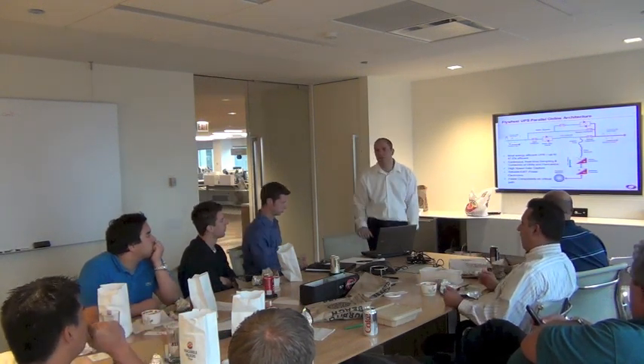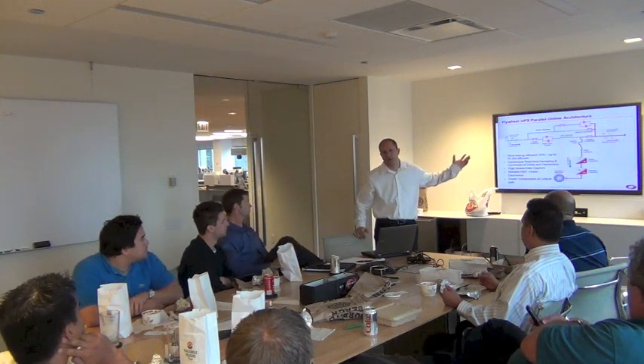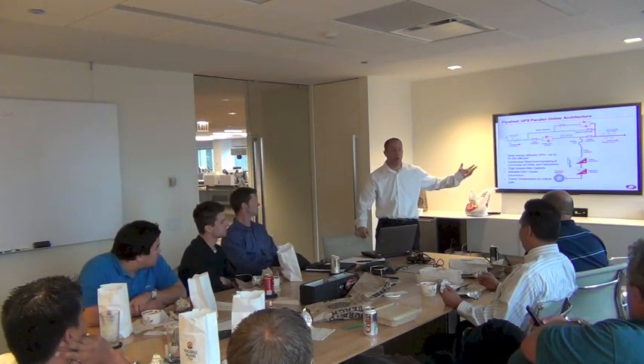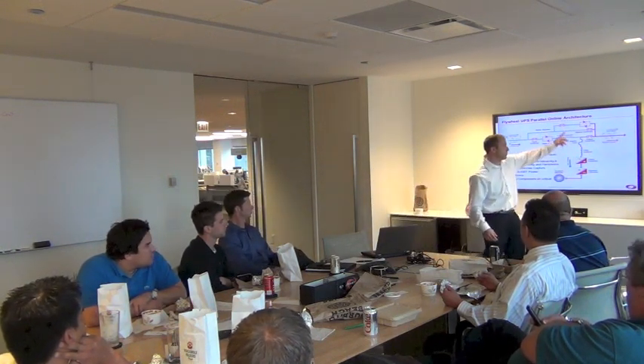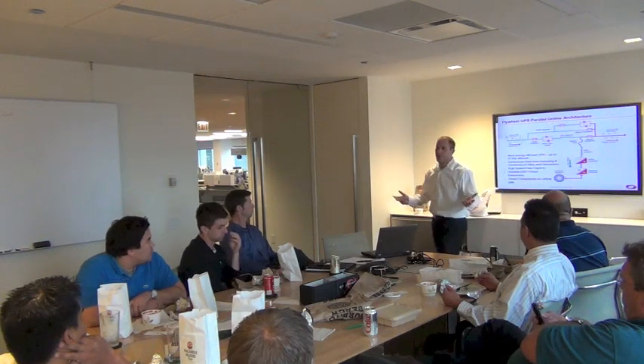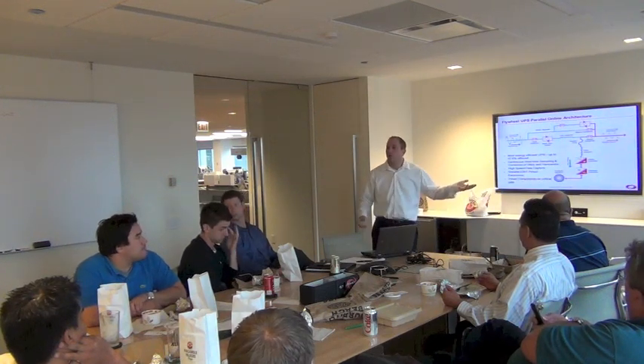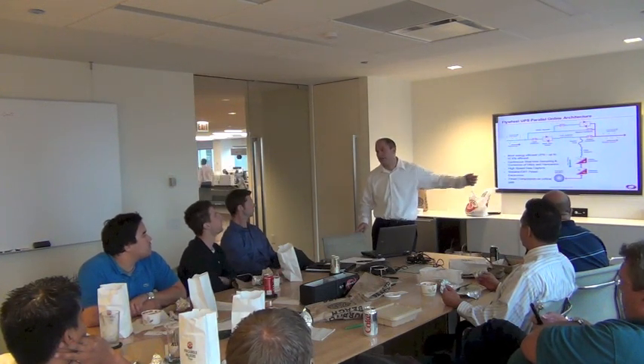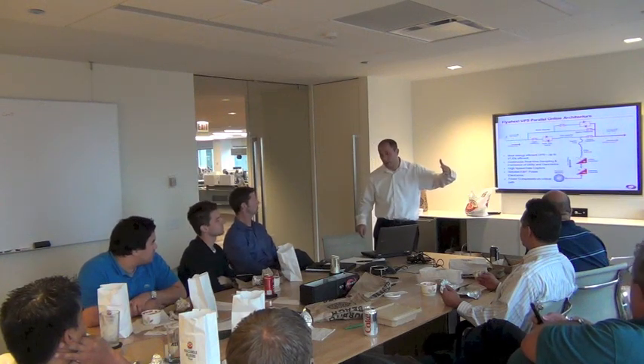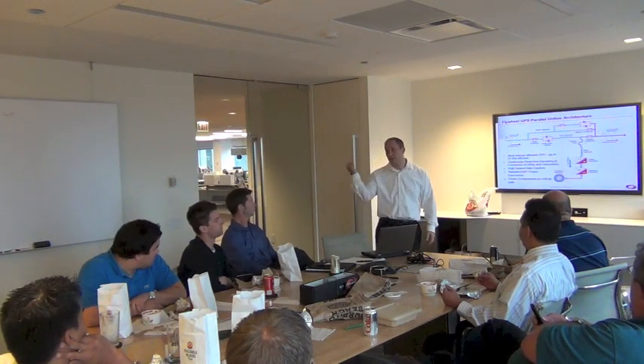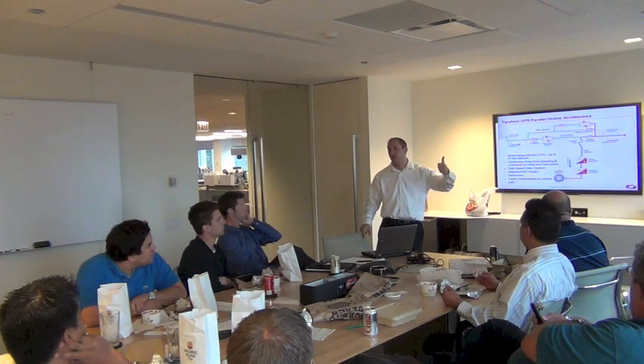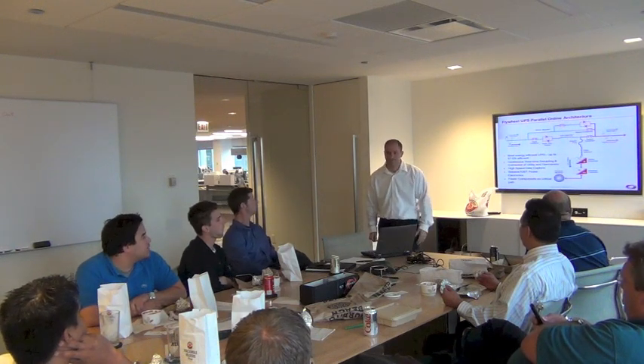And we've seen both 3-wire and 4-wire plus ground systems. For a 3-wire plus ground system, we have what's referred to as a zigzag transformer on the outputs. We derive the neutral when we go into discharge. With a 4-wire plus ground system, you're going to run all 3 phases, the neutral, and ground to the UPS. And in normal operating mode, we're deriving the neutral at the source.